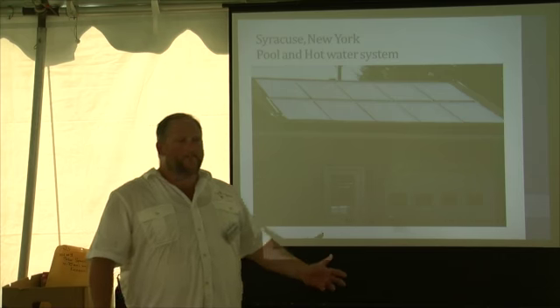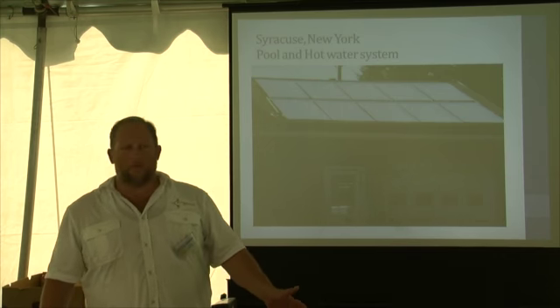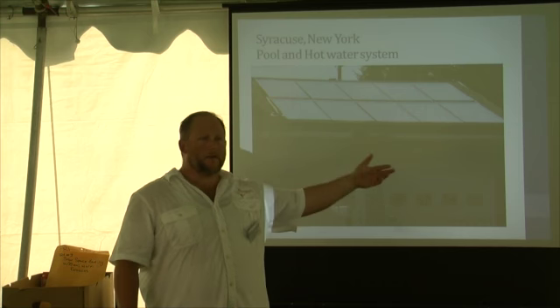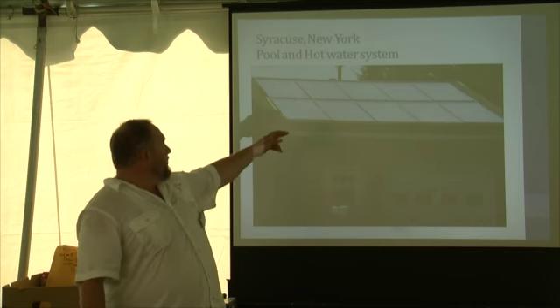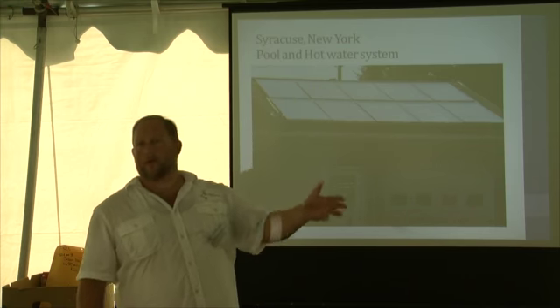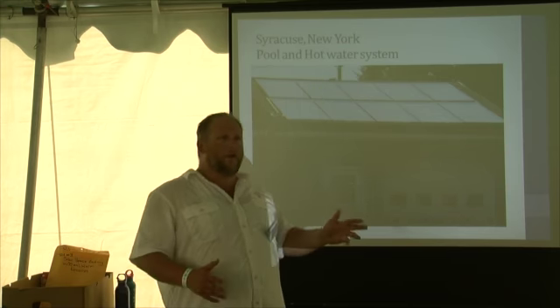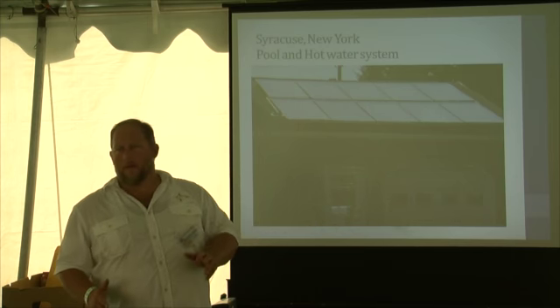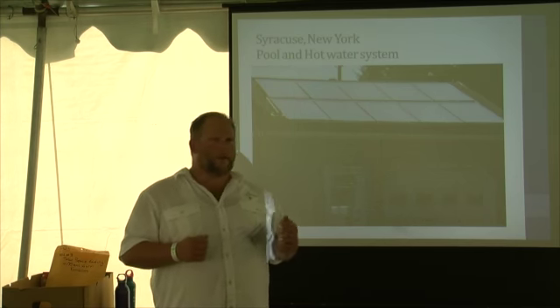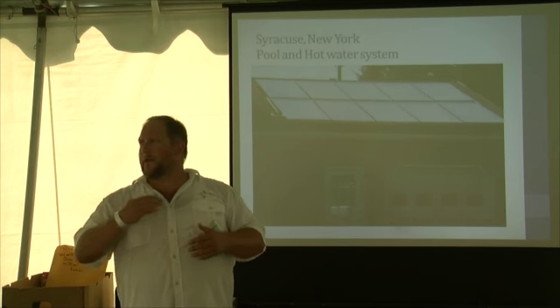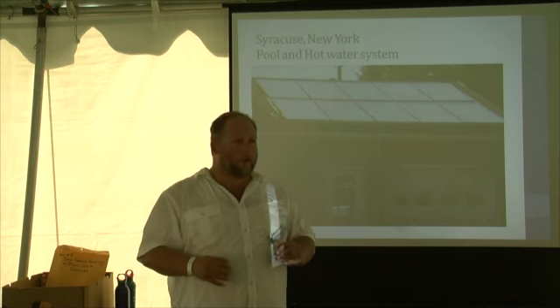So here we have a nice balanced system, very symmetrical. We got 5 collectors on the bottom row, 5 collectors on top. There's a way you can plumb this called reverse return. But if I didn't plumb this in reverse return, I could use balancing valves. The bottom line is you've got to make sure you have equal flows through both collectors.